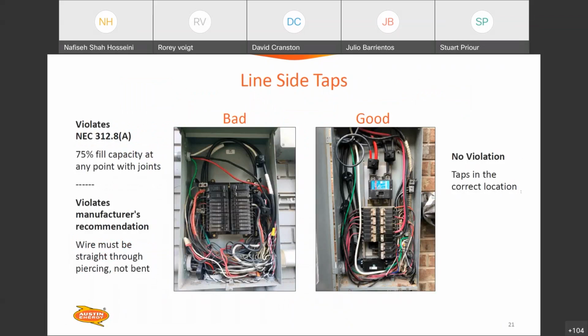Here are two examples, bad and good. Notice on the left where those taps are. The panel is chock full. It wouldn't necessarily be a problem to have a backfeed breaker in that panel even though it's full, but you can see those taps are placed on the side of the panel, which violates the NEC's 75% fill rule. With those taps, you're potentially putting mechanical stress on the main breaker and on other circuits in that panel.